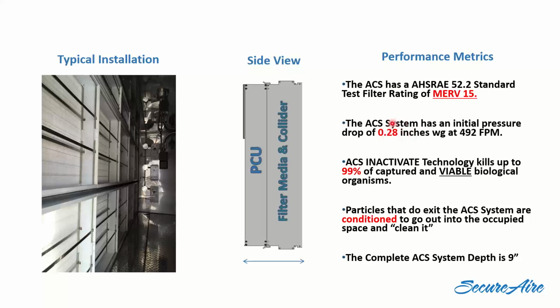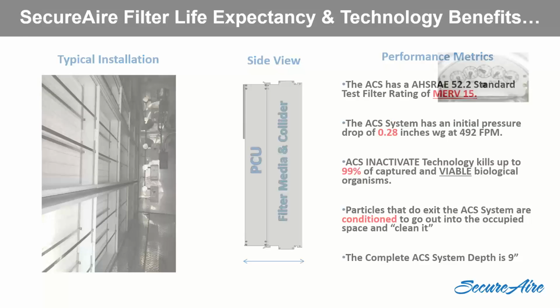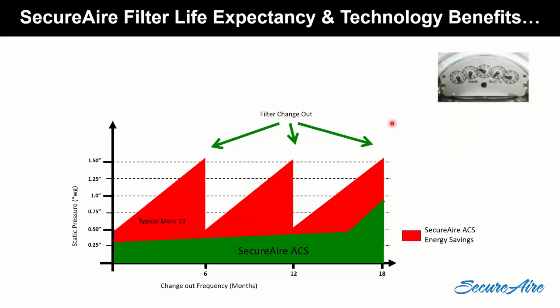So this is definitely manageable for most existing air handlers. If your air handler has the space to put this in, and the fan is a VFD controlled fan and we can speed it up just a tiny bit, this is probably the way to go because it's a really good filter and it helps attack stuff in the space. Additionally, the filtration actually lasts a long time.